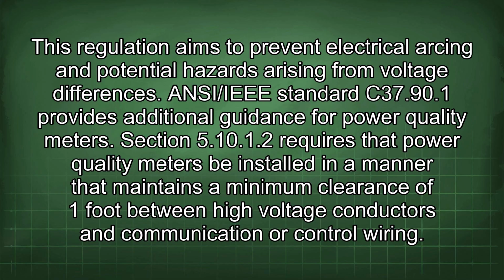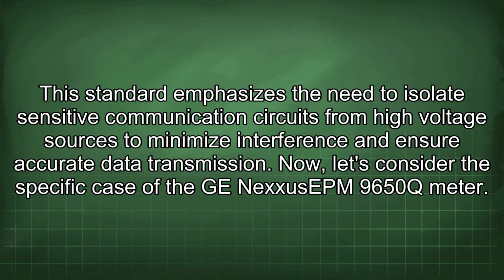ANSI/IEEE Standard C37.90.1 provides additional guidance for power quality meters. Section 5.10.1.2 requires that power quality meters be installed in a manner that maintains a minimum clearance of 1 foot between high voltage conductors and communication or control wiring. The standard emphasizes the need to isolate sensitive communication circuits from high voltage sources to minimize interference and ensure accurate data transmission.